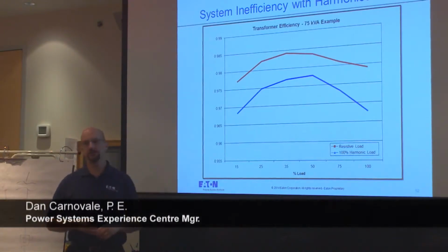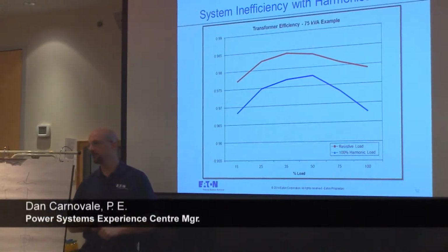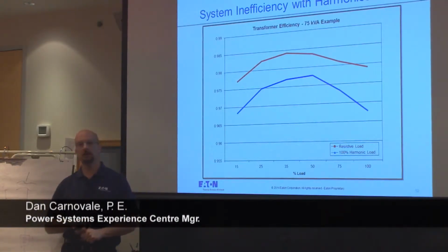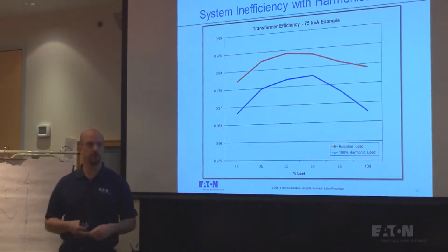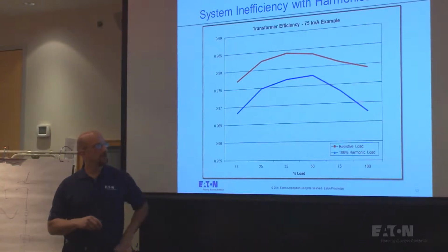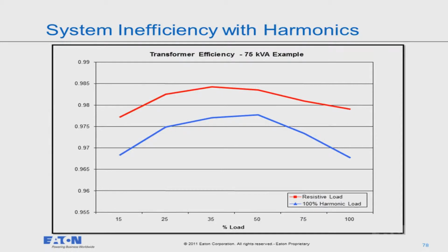Here's the thing on efficiency. I did a measurement with a 75 kVA transformer. I put a really bad harmonic source on, which was a bunch of computer power supplies, and I distorted the voltage and I distorted the current. And I looked at, with a resistive load compared to that 100% harmonic load, what's the efficiency difference on a standard transformer? Across the range of loading, it's about a 1% change.